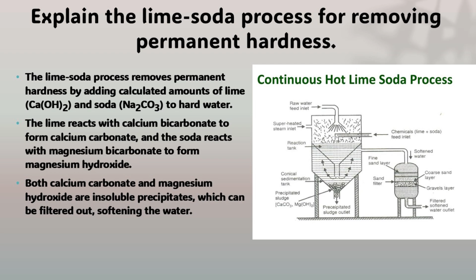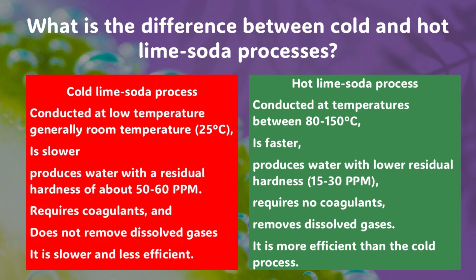The next question is question number 28. What is the difference between cold and hot lime soda processes? The answer to this question is cold lime soda process, conducted at room temperature, 25 degrees Celsius, requires coagulants and produces water with a residual hardness of about 50 to 60 ppm. It is slower and less efficient. Hot lime soda process, conducted at temperatures between 80 to 150 degrees Celsius, is faster, produces water with lower residual hardness, 15 to 30 ppm, requires no coagulants, and removes dissolved gases. It is more efficient than the cold process.